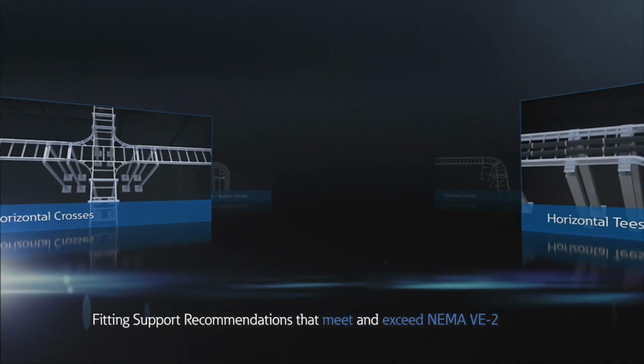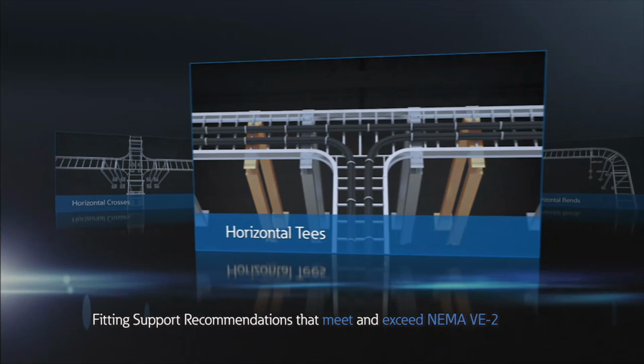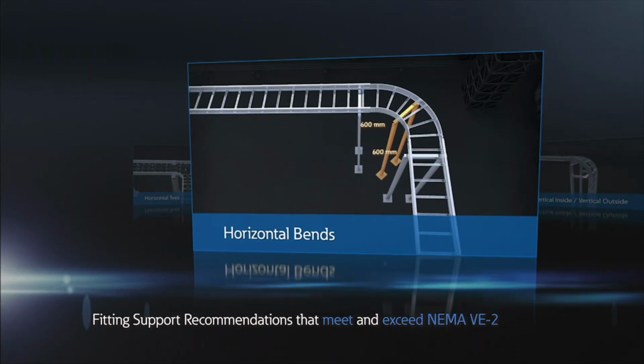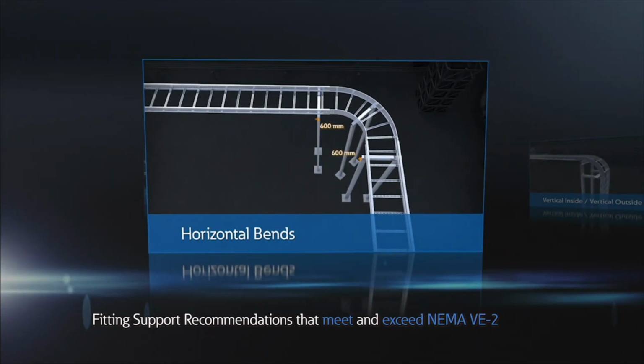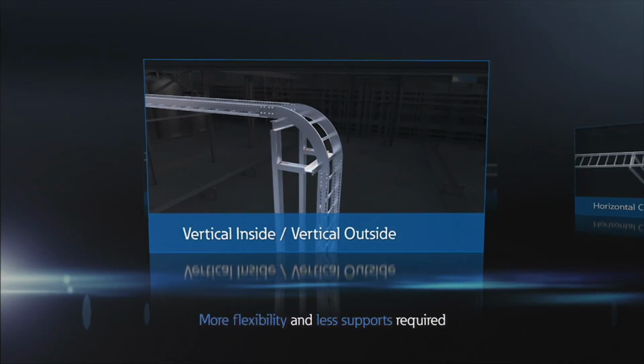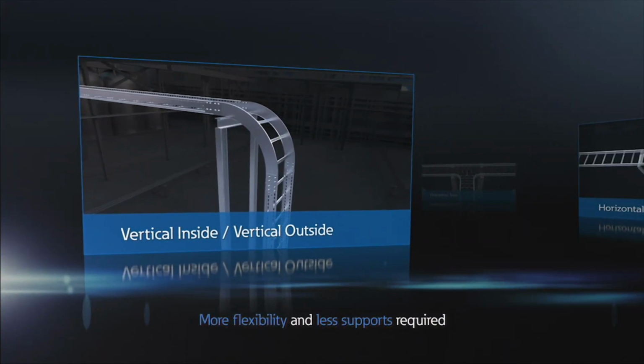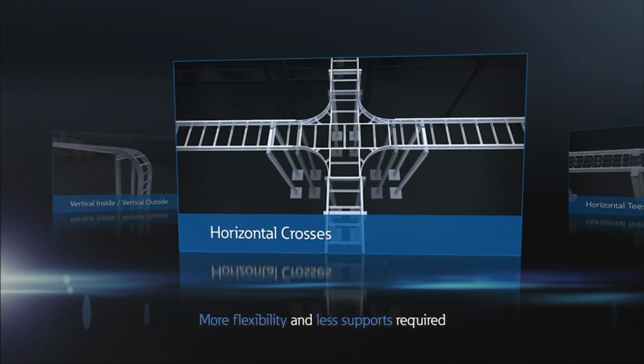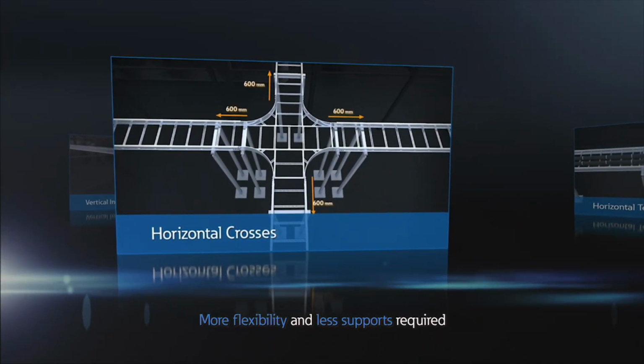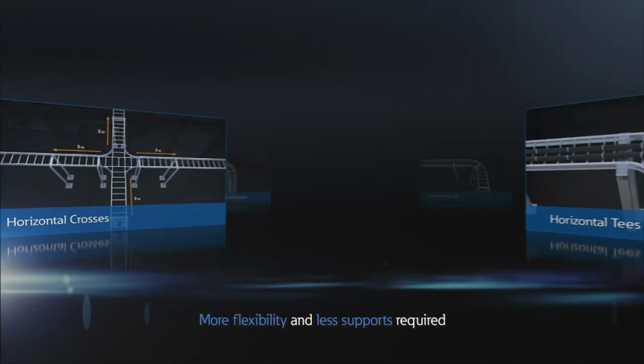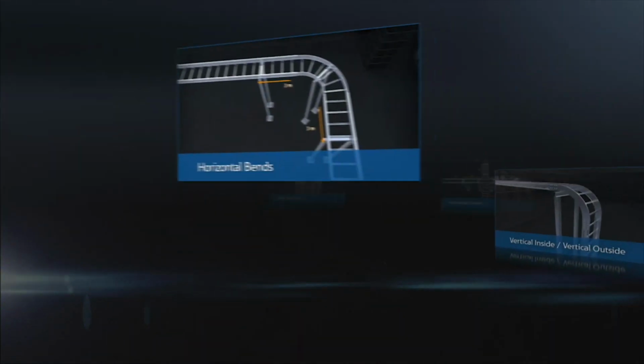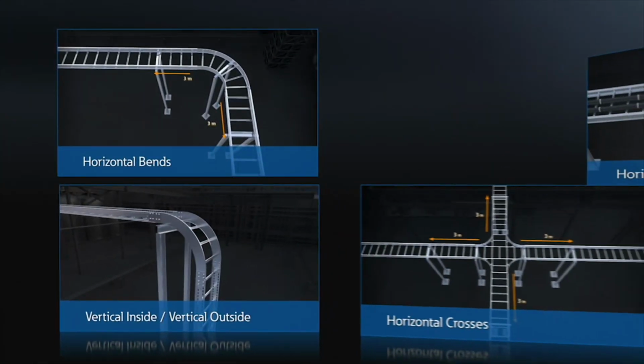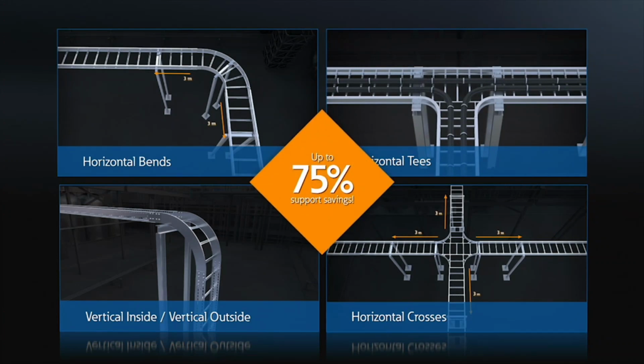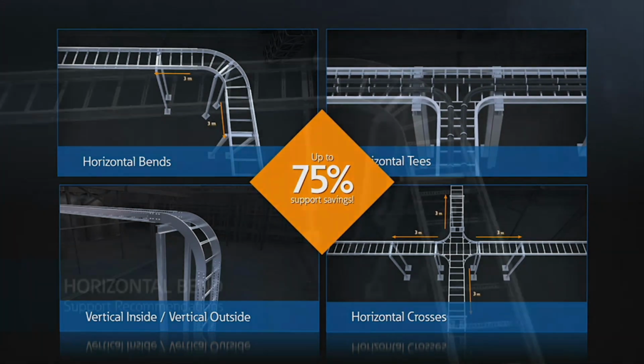In addition, Eaton has created recommendations for its B-Line series fittings that fully comply with and exceed NEMA VE2 support recommendations. Our systems feature industry-leading 75mm to 100mm tangents that are specifically engineered to help maximize strength and carrying capacity of the complete system. Depending on the fitting being utilized, the installer can save up to 75% on support costs.